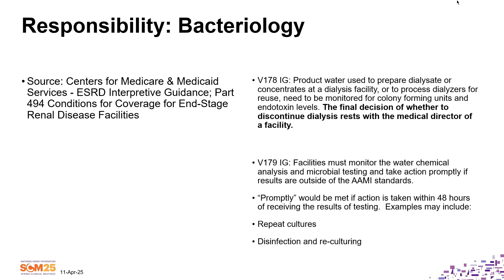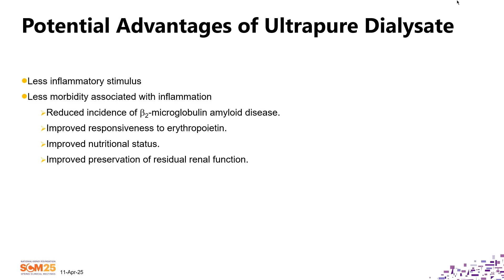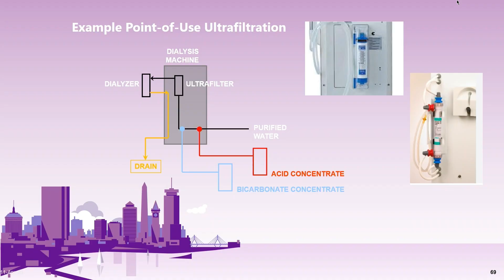So there is no such thing. It's a medical director's assessment as to what to do. And I'm almost at potential ultrapure dialysate. That secondary filter in the back of the machine, an option, and the other machines have the option too, is to actually deliver what we can now deliver as ultrapure quality, which is the 0.1, 0.3 levels of contaminant. What it does is it's less inflammatory stimulus, less morbidity associated with inflammation, reduced incidence of beta-2 and so forth. It's in the slide so you can read it afterwards because I'm going to go fast.